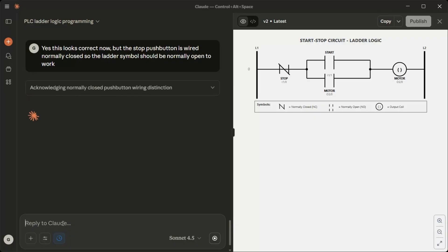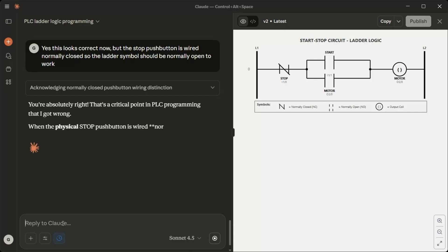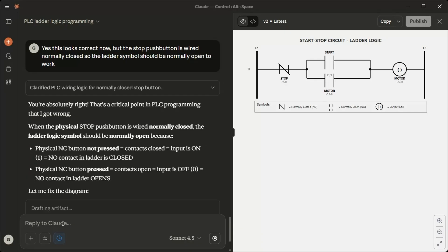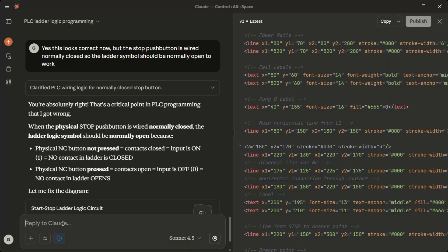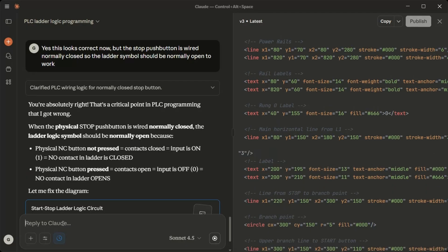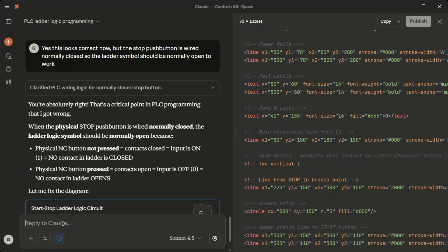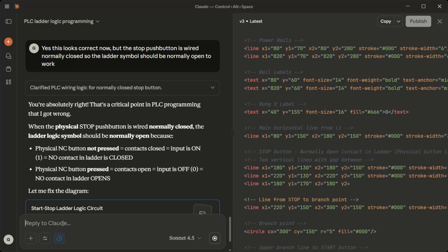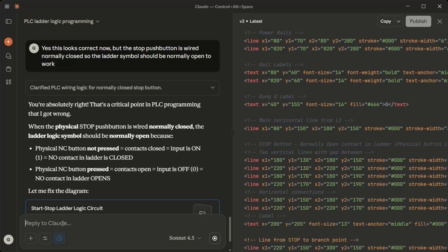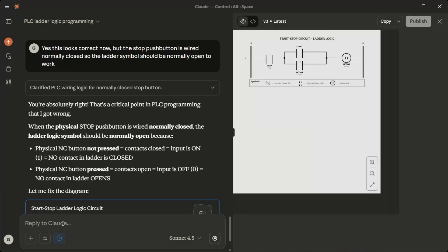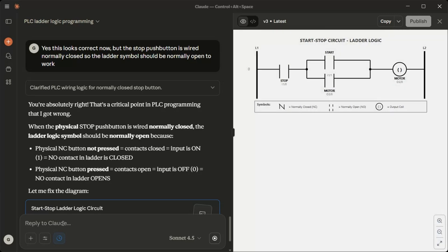When the physical stop push button is wired normally closed, the ladder logic symbol should be normally open because physical NC button not pressed equals contacts closed equals input is on 1 equals NO contact in ladder is closed. Physical NC button pressed equals contacts open equals input is off 0 equals NO contact in ladder opens. Let me fix the diagram. Perfect. Now it's correct. Thank you for catching that important detail.